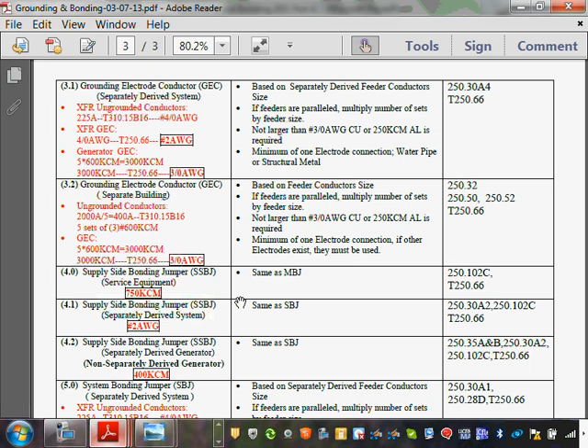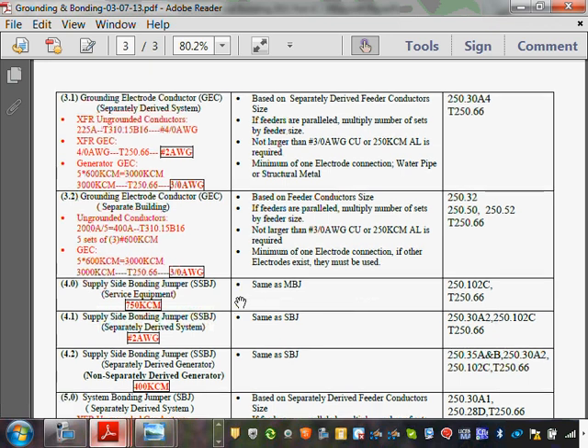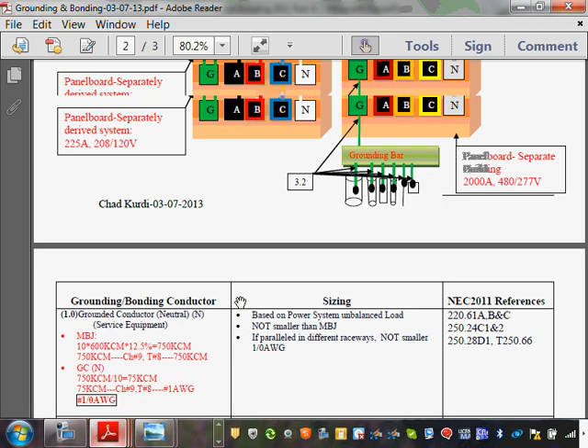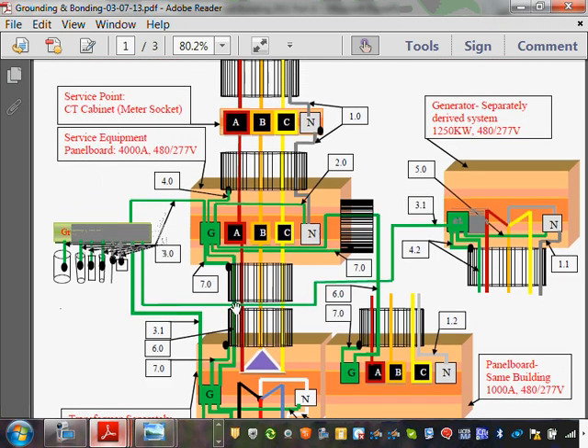Any comments, guys, about the supply side bonding jumper? Okay, so that's your supply side. Why do they call it supply side? Because it's on the supply side of the service disconnect means, right? That's your supply side bonding jumper, exactly like the main bonding jumper in terms of size. So that's 4.0. So now we grounded the conduits to the box.